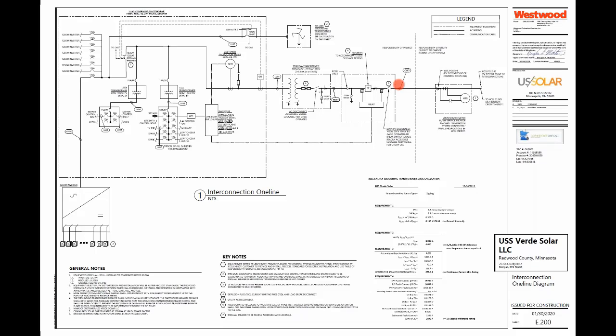Similar to that original installation we showed you, there is a zigzag transformer at the top of the customer print. That has been cleaned up a little, where in this installation they do not have a protective relay. So that little circuit breaker connecting to the zigzag transformer is what, in the event of a fault condition, will trip open the main breaker and disconnect it from the grid. In this case, the transformer is a 600 to 13.8 conversion. So the paralleling on the AC board is being done at 600 volts.